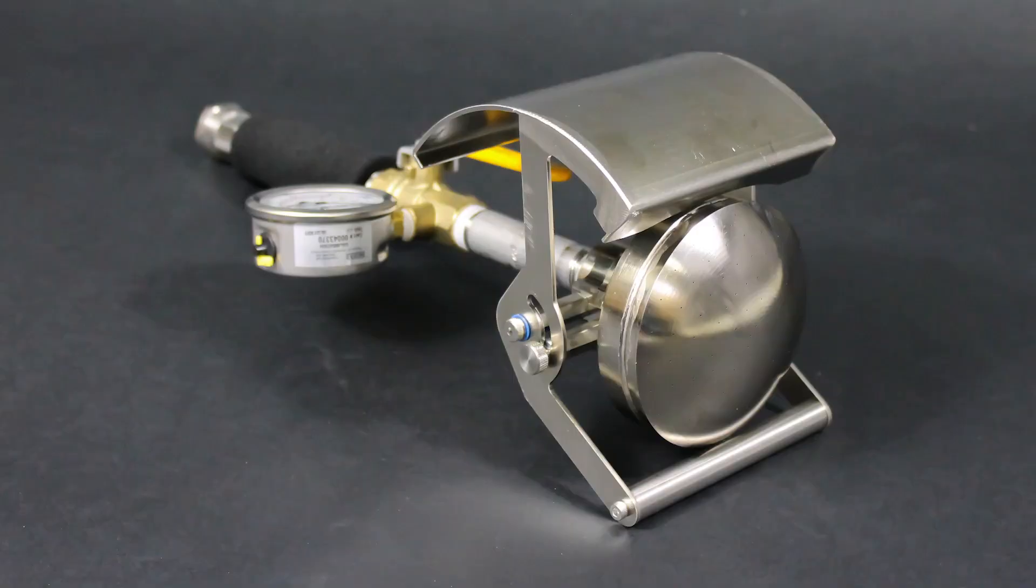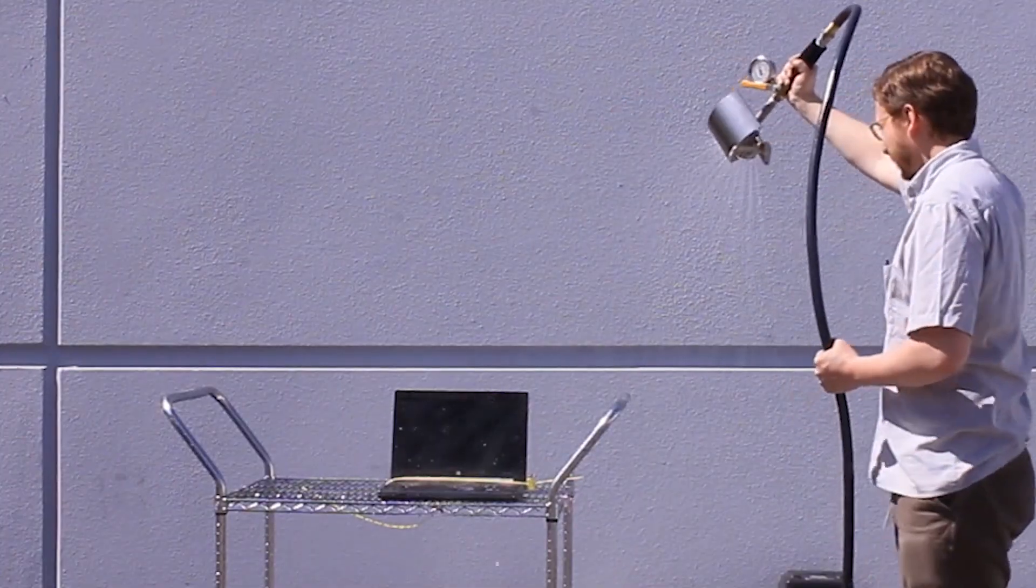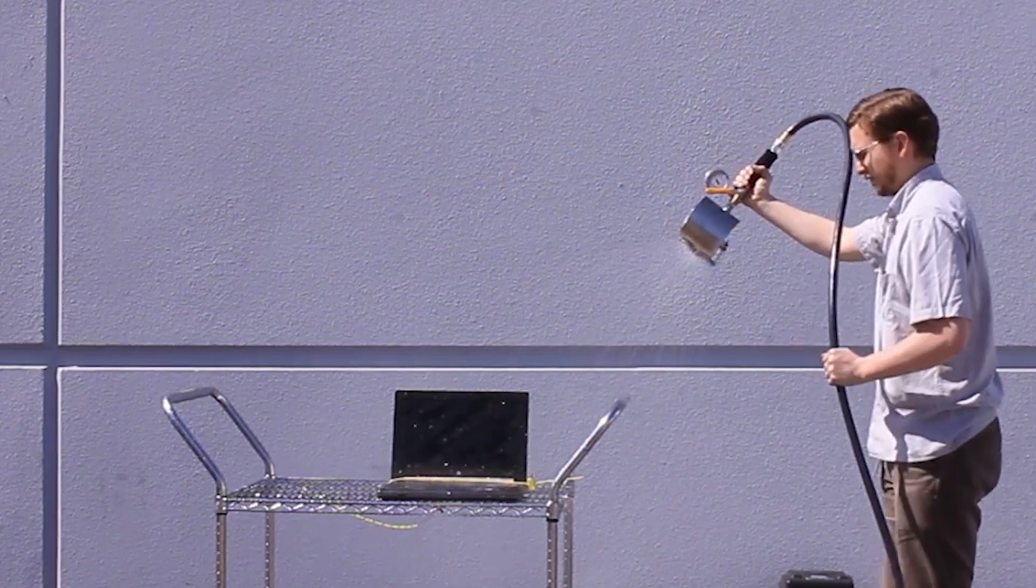The shower head type nozzle allows us to test to a standard called IEC 60529 levels three and four, and that specific nozzle allows us to simulate rainfall at vertical or near vertical orientations.